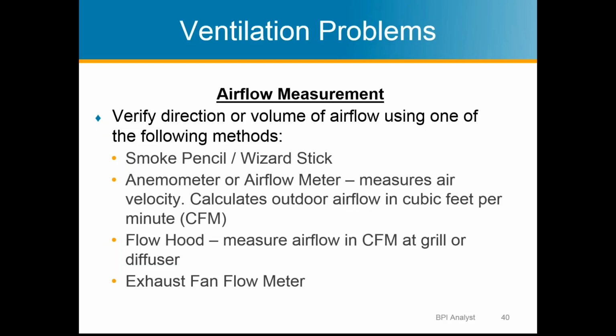And it's really surprising how many times vent fans are installed backwards, so that the air is actually blowing in instead of blowing out. That could be intentional, but I've never found one installed backwards intentionally. You can also use an anemometer that just measures airflow, measures air velocity, and then through some calculations, figure out the cubic feet per minute that's leaving.